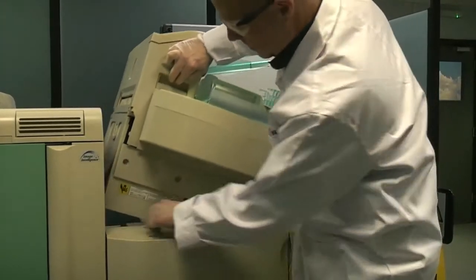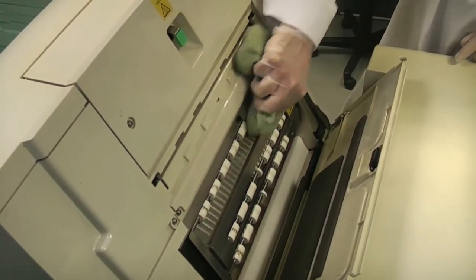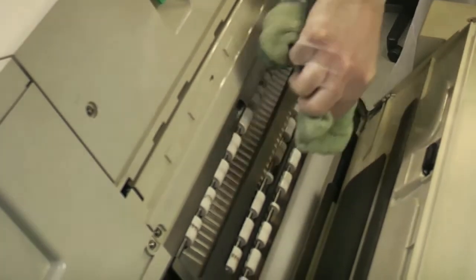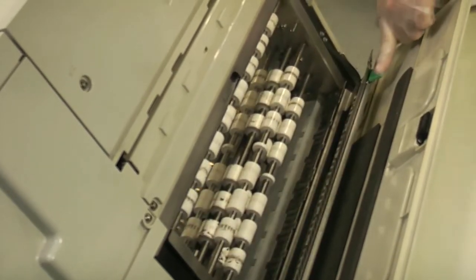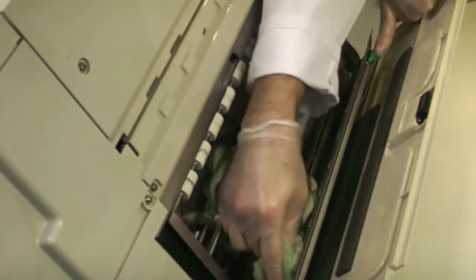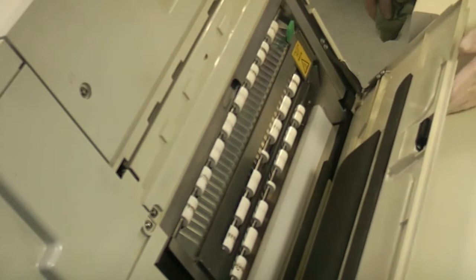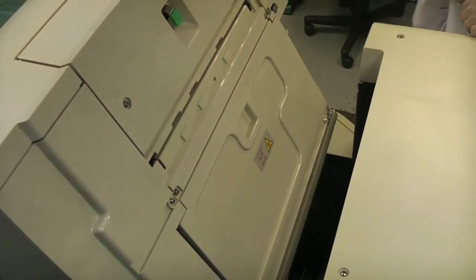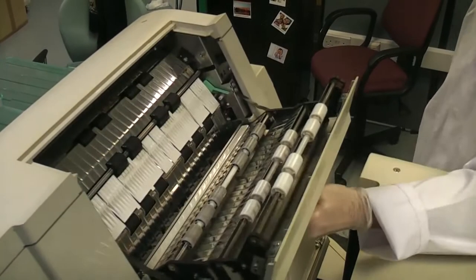Open the dryer unit by releasing the lock and support it using the green stopper. Open the lower section cover and clean the rollers and surfaces using a damp cloth. Repeat the process for the upper section of the dryer unit.